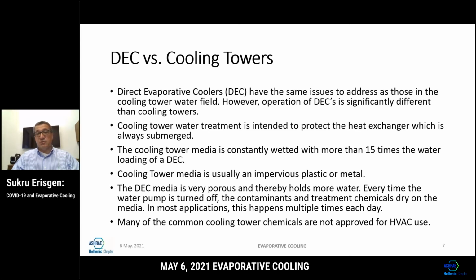Cooling tower water treatment is intended to protect the heat exchangers, which are always submerged, as you know. And cooling tower media is constantly wetted, with on average more than 15 times the water loading of direct evaporative coolers. What I mean by this is that with direct evaporative coolers, the wetted media needs to be dried every so often. Most people try to dry the media once a day to prevent algae and bacteria growth. Because the use of chemicals is restricted, at least in the United States and some other countries, what kind of chemicals can be used is very different. Cooling towers can use chemicals that are not allowed in buildings.